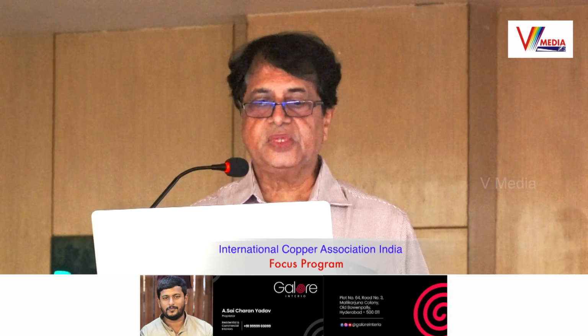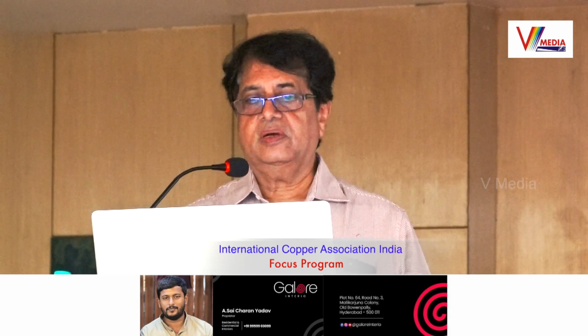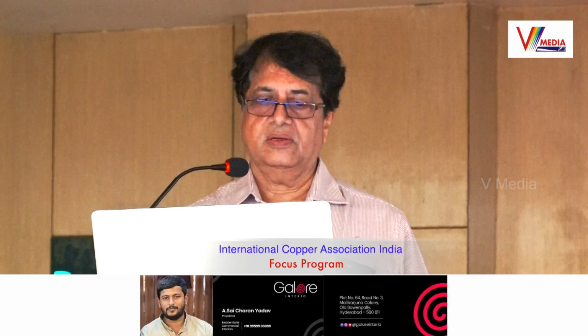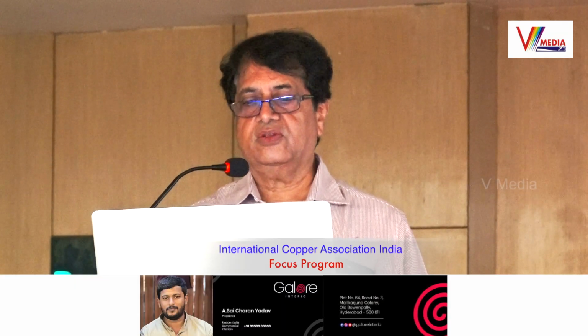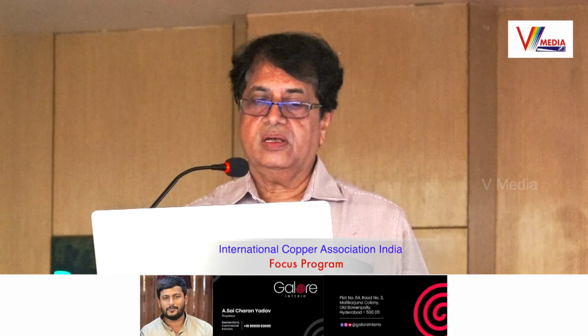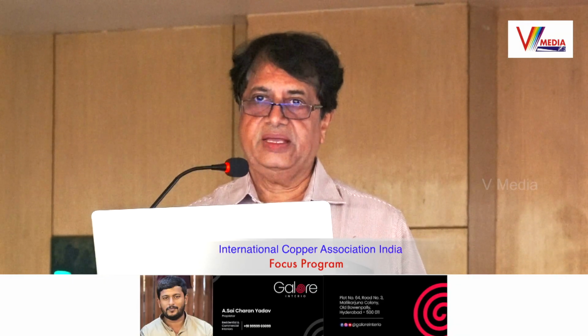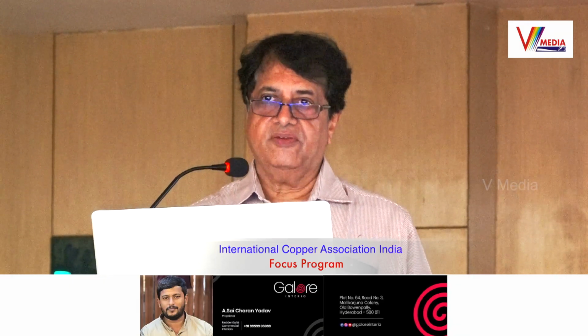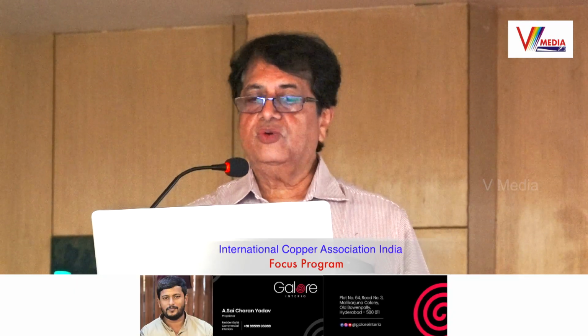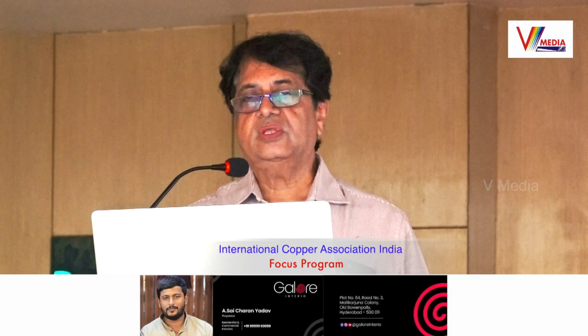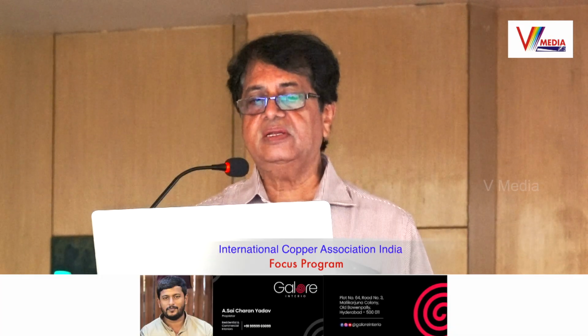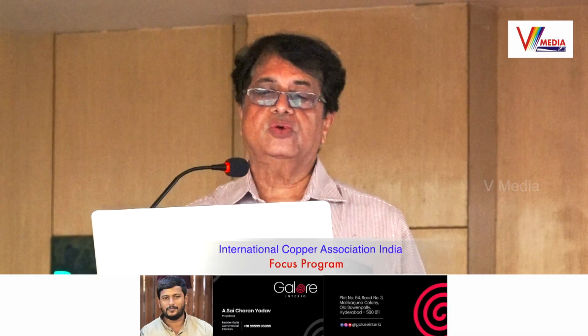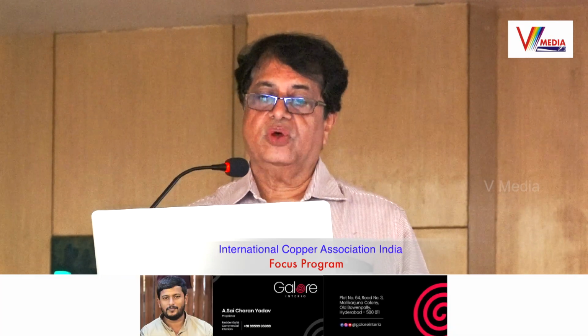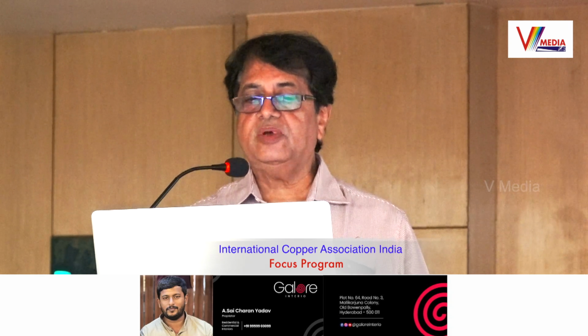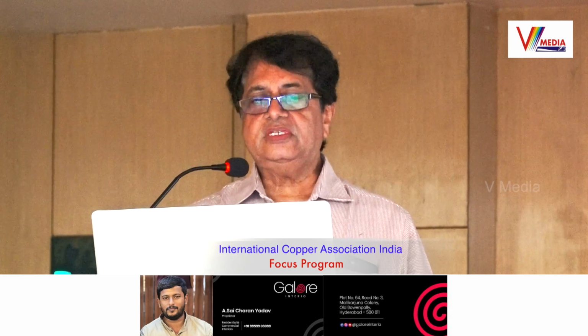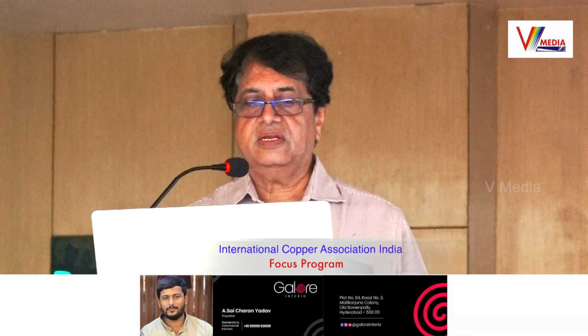In the recent edition which was published in June 2023, certain amendments have been made by the Central Electricity Authority in respect of lines which cross the national highways. It is now mandatory to use underground cable only for lines up to 22 kV, and above that the clearance which was previously required, about 5 to 7 meters from the finished road level, has now increased to a minimum of 11.6 meters. This is another point which is again given in the National Electrical Code.